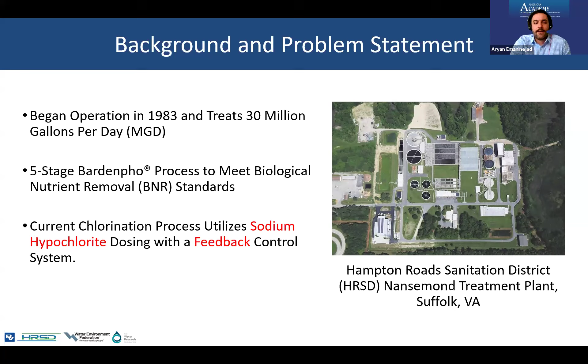The way they're doing that is based on a feedback control system that tells them how much sodium hypochlorite to dose. One issue is that it's a very expensive chemical. If you use too much, you're going to waste a lot of money. If you use too little, you're risking your discharge limits. So there's always a sweet spot here.